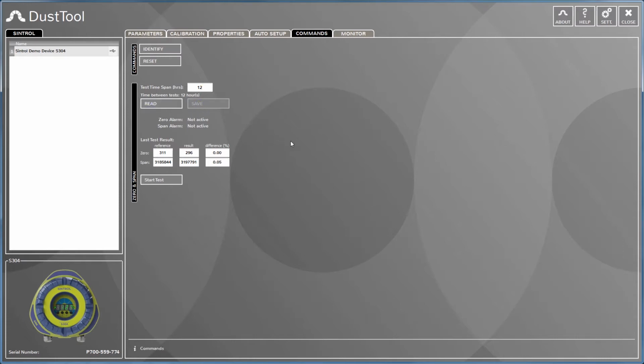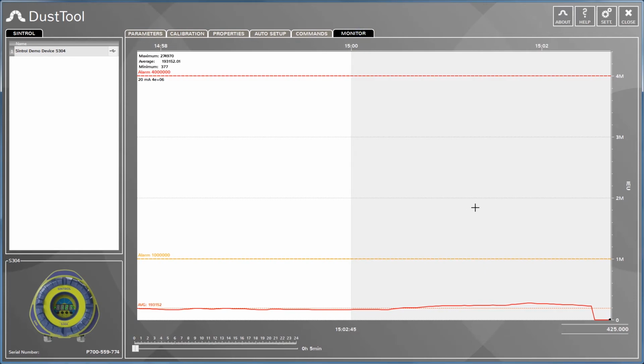It will take a couple of seconds and then the instrument will start right away. Here it goes, a first zero and span check. We can go to the monitors view. You can see now it has switched from measurement mode to 0 or 4 milliamps, and in about 2 minutes it will go up to 80% of span or 16.8, 16.9 milliamps.